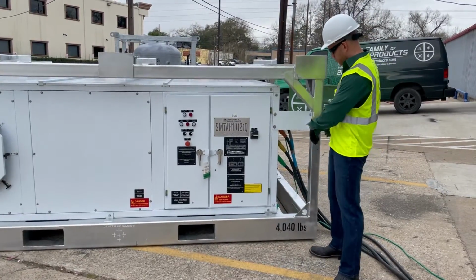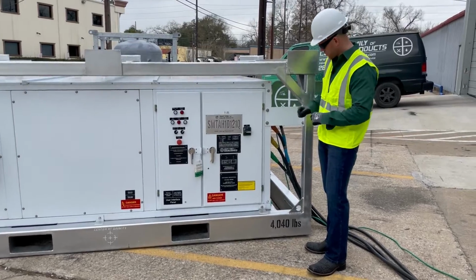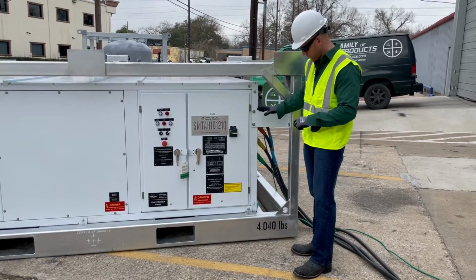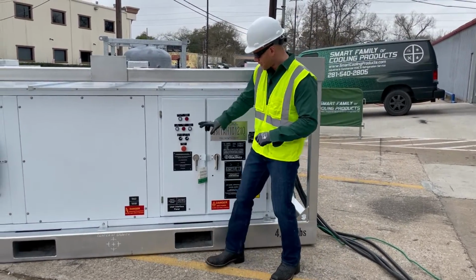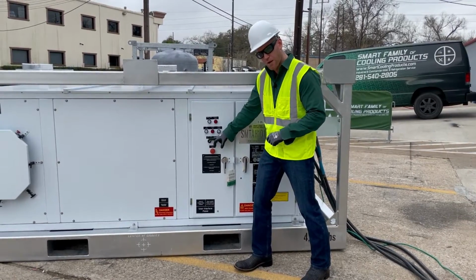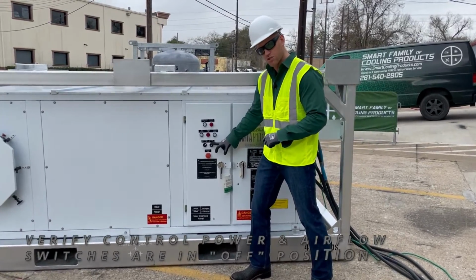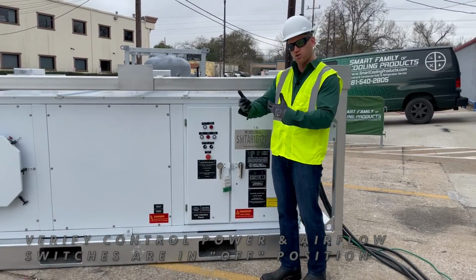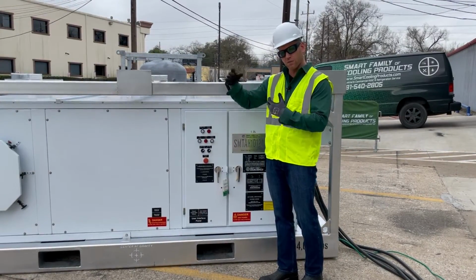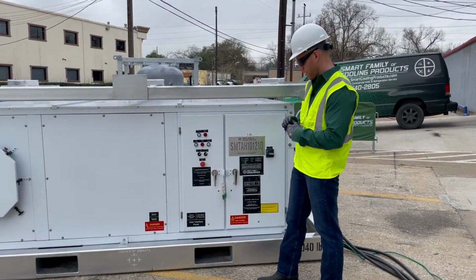Okay, putting the correct power to the machine, that's your responsibility. We've done that here. Okay, when we're ready to run, I want to make sure that my control power switch is off and my airflow switch is off, because I only want to get control power and run the blower to generate airflow when I'm ready for it. So both of those are in the off position.